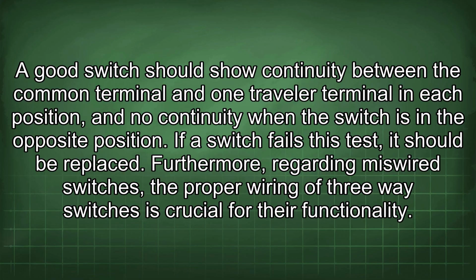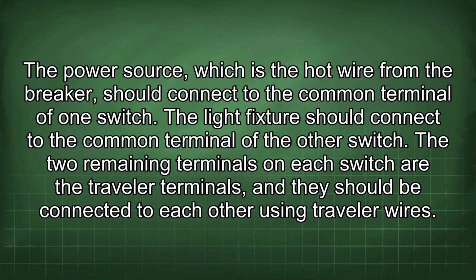Furthermore, regarding miswired switches, the proper wiring of three-way switches is crucial for their functionality. The power source, which is the hot wire from the breaker, should connect to the common terminal of one switch.